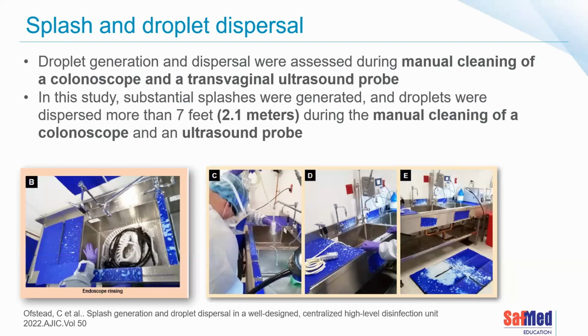If you look at the images there, what they did is they took a particular paper material that reacts to splashes by changing color, so you can see all over the department how far things have actually splashed. Droplets can be dispersed up to 2.1 meters during the manual cleaning of a colonoscope. So if you think about it, if the only cleaning process is next to the patient's bed, or we're doing all of this right next to the patient's bedside in the operating room, are we not contaminating that area? Is it really the right thing to do?